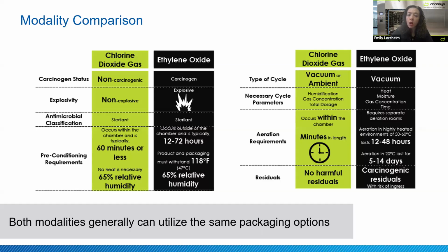Now, some differences here. For the majority of products and situations, I should say, the entire process occurs within the chamber. So this includes everything from preconditioning through aeration. Preconditioning generally is 60 minutes at ambient temperature, whereas with ethylene oxide, this can last for many hours to even days and often is a heated environment. So if you have a temperature sensitive device, it's not necessarily compatible. Now, you do want to humidify your product in your sterilization load. This is to open up spore walls to allow a sterilant to penetrate. Now, this is roughly between 65 and 75% relative humidity. But again, chlorine dioxide requires a much shorter time.